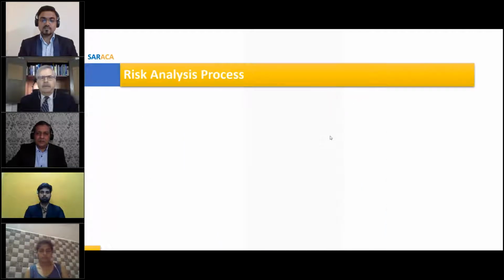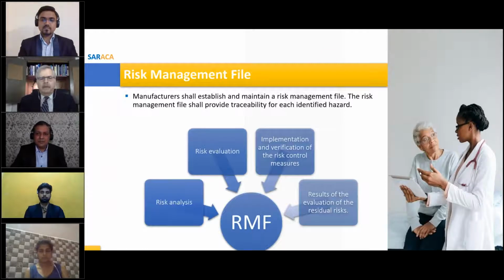The other change that's occurred with the 2019 edition is that top management has to define what risk they will accept. And the other thing is that the risk management file and the evaluation of your risk must be reviewed at planned intervals. That's not part of the QMS quality management review, however often you do it, annual or semi-annual. It's a specific planned review of your risk analysis, done by management or appointed personnel who have the authority and the background to be able to do a thorough risk analysis. I just wanted to point those out because those are some additions that are somewhat new to this standard.